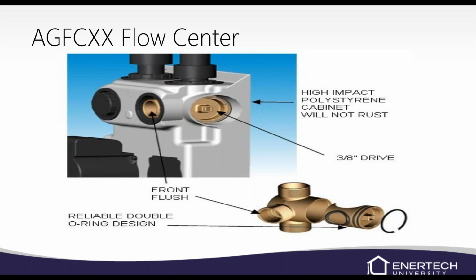Again, this is a breakout of the three-way valve if you were to pull it out of that flow center. There are gaskets and a snap ring that can be replaced if the three-way valve is leaking. A lot of times you'll see a little bit of water coming out between that plastic and that brass piece, dripping down the side of the flow center. That's an indication that those seals are leaking. If it's out of warranty, then you can get a gasket kit. It'll come with 3 gaskets and a new snap ring. So it can be repaired.